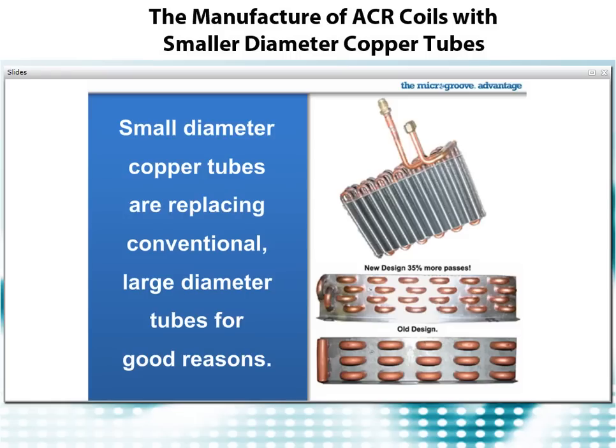This photo represents a real-life example of what we just reviewed, taken from a catalog on the Internet. The new design shows smaller diameter tubes providing 35% more passes, resulting in considerably more heat transfer. The tubes in the new design are arranged in a staggered pattern, which will further improve the efficiency of the coil. This ability to arrange tubes in more efficient geometric patterns is yet another advantage of round copper tubes.